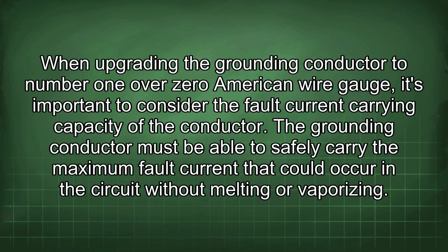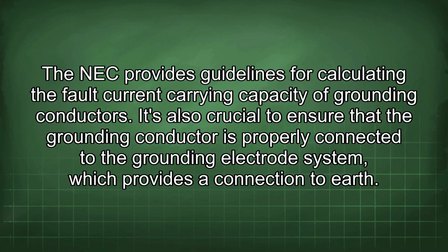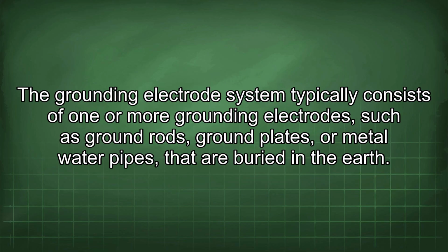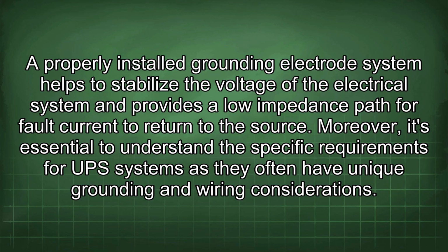When upgrading the grounding conductor to number 1/0 American wire gauge, it's important to consider the fault current carrying capacity of the conductor. The grounding conductor must be able to safely carry the maximum fault current that could occur in the circuit without melting or vaporizing. The NEC provides guidelines for calculating the fault current carrying capacity of grounding conductors. It's also crucial to ensure that the grounding conductor is properly connected to the grounding electrode system, which provides a connection to earth. The grounding electrode system typically consists of one or more grounding electrodes, such as ground rods, ground plates, or metal water pipes, that are buried in the earth. A properly installed grounding electrode system helps to stabilize the voltage of the electrical system and provides a low impedance path for fault current to return to the source.